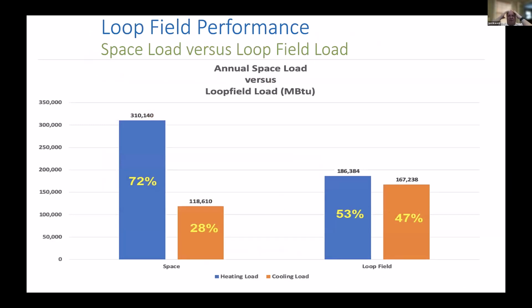Now, why is that? It's important to understand that the space load is very different from the actual loop field load. For example, on an annual basis, the annual space load for heating purposes was actually 310,000 MBTUs. The cooling was much less. So there was only about a 72-28% ratio. However, the loop field almost saw the same amount.